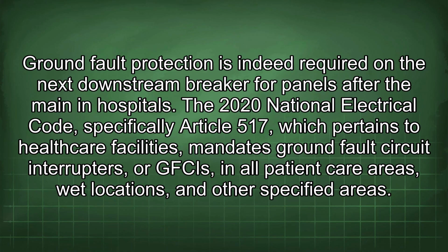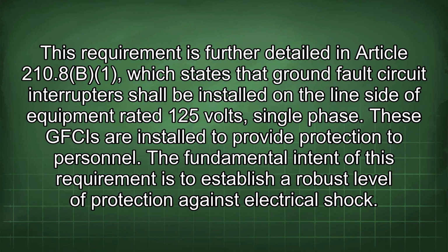Ground fault protection is indeed required in the next downstream breaker for panels after the main in hospitals. The 2020 National Electrical Code, specifically Article 517, which pertains to healthcare facilities, mandates ground fault circuit interrupters, or GFCIs, in all patient care areas, wet locations, and other specified areas. This requirement is further detailed in Article 210.8, which states that ground fault circuit interrupters shall be installed on the line side of equipment rated 125 volts, single phase.